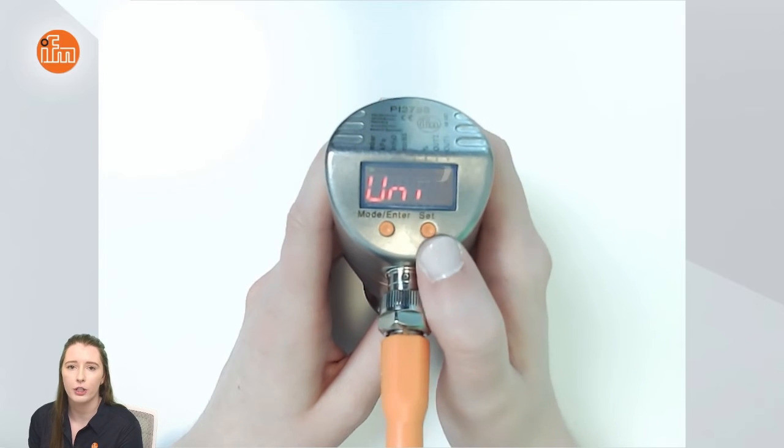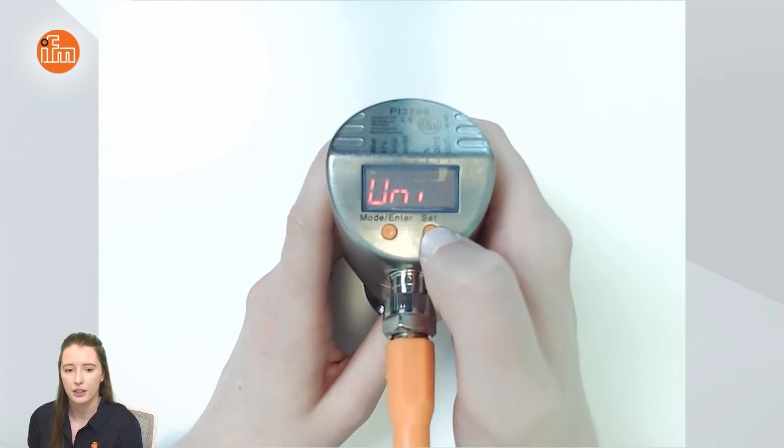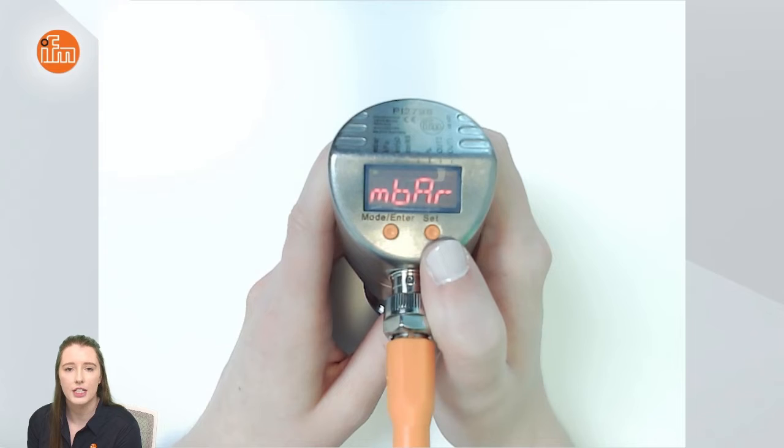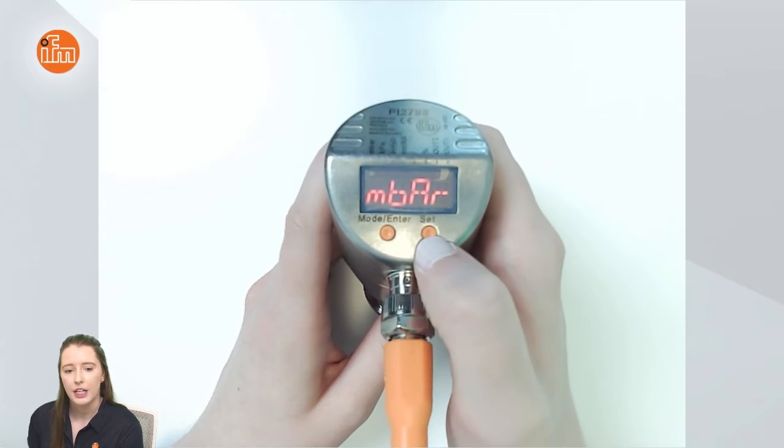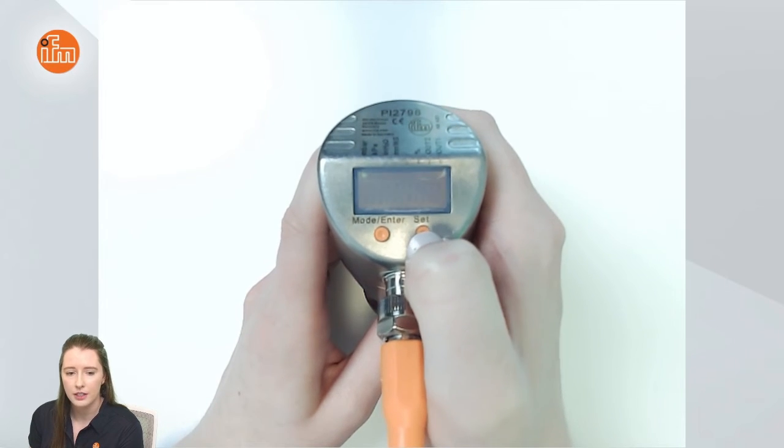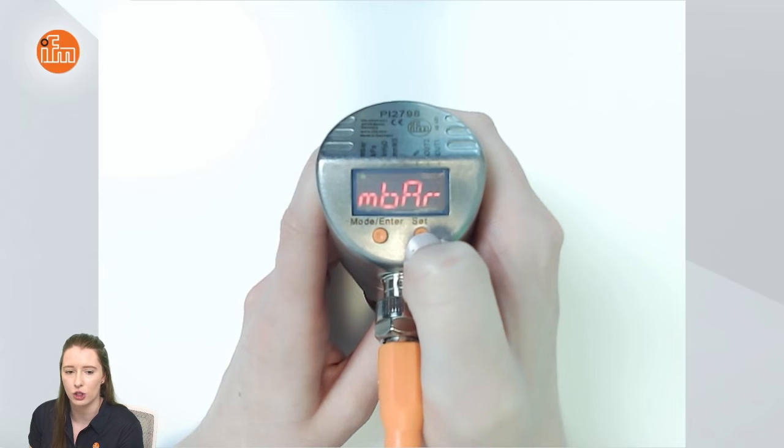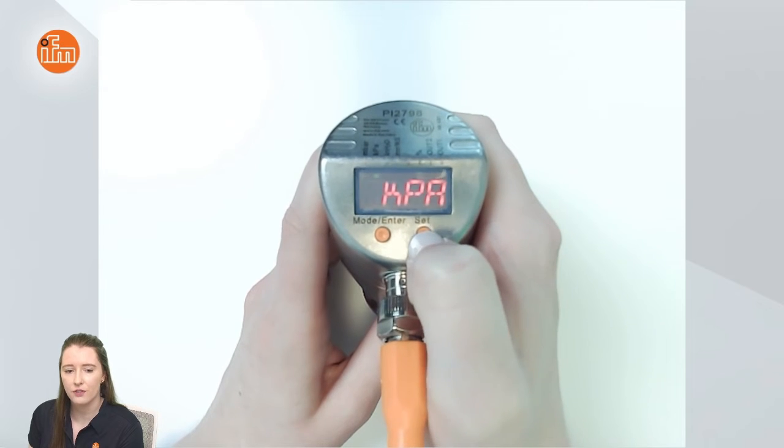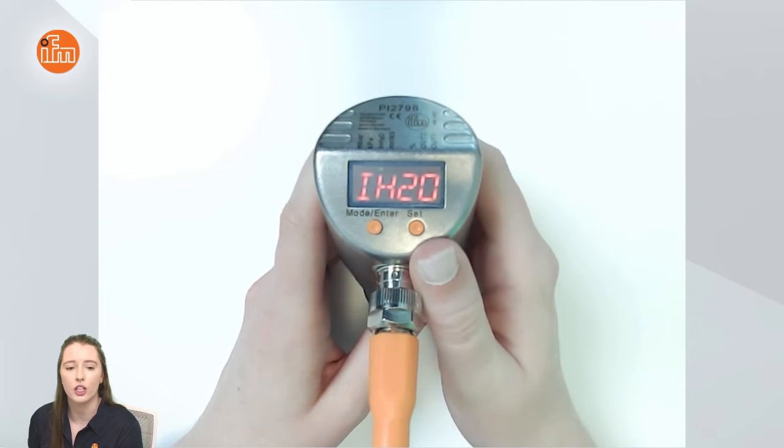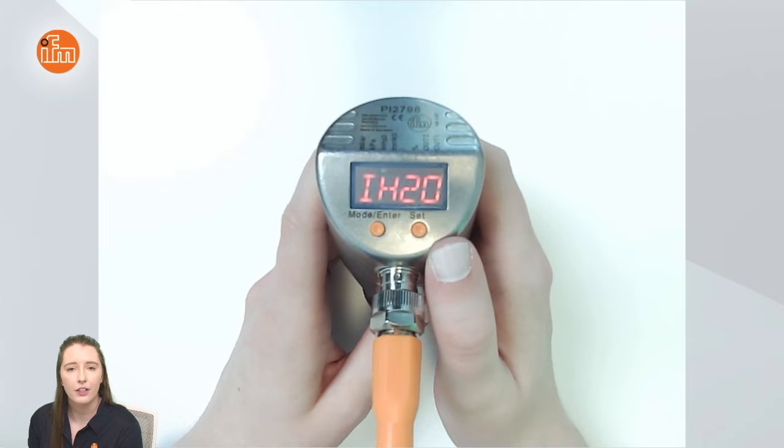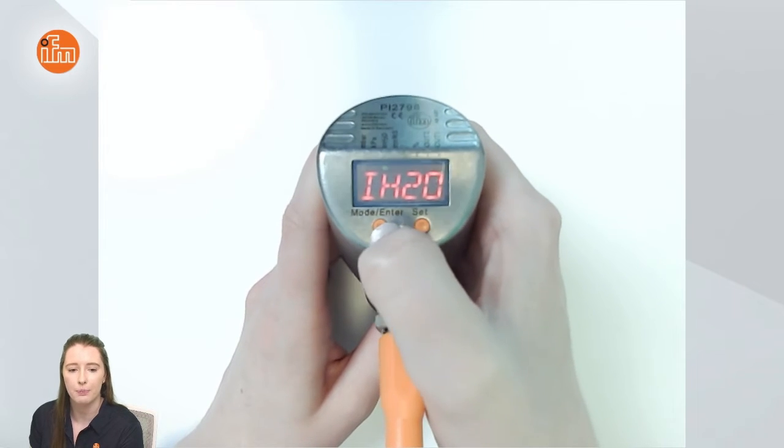Here you will see uni where you can change your units of display. So if I press set you'll see it as factory set for millibar and if I hold down the set button the display will begin to flash and then scroll through your options. So for today's video I'm going to set it for inches of water column. Once you have it on what you want to set it for you would press mode enter.